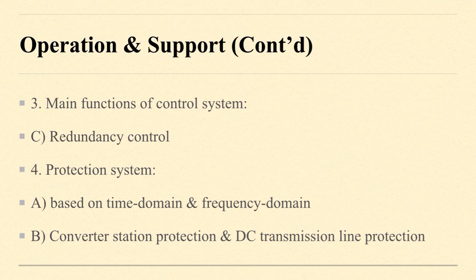Second is converter station protection and DC transmission line protection. The converter protection is the core of converter station protection. The converter protection can be divided into over current protection, over voltage protection, valve short circuit protection, and so on. Actually, how to make full use of the control function to limit and eliminate faults is the difficulty of the future research.